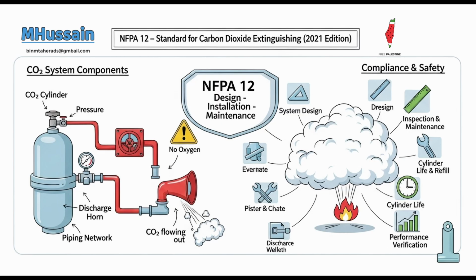For manual controls, there are specific ergonomic requirements. They must not require a pull force of more than 40 pounds (178 newtons). Not too hard to pull. Or a movement of more than 14 inches (356 millimeters), ensuring they can be operated quickly and effectively in an emergency. And at least one manual control must be positioned no more than 4 feet (1.2 meters) above the floor for easy access by most adults. Easy to reach, easy to operate.